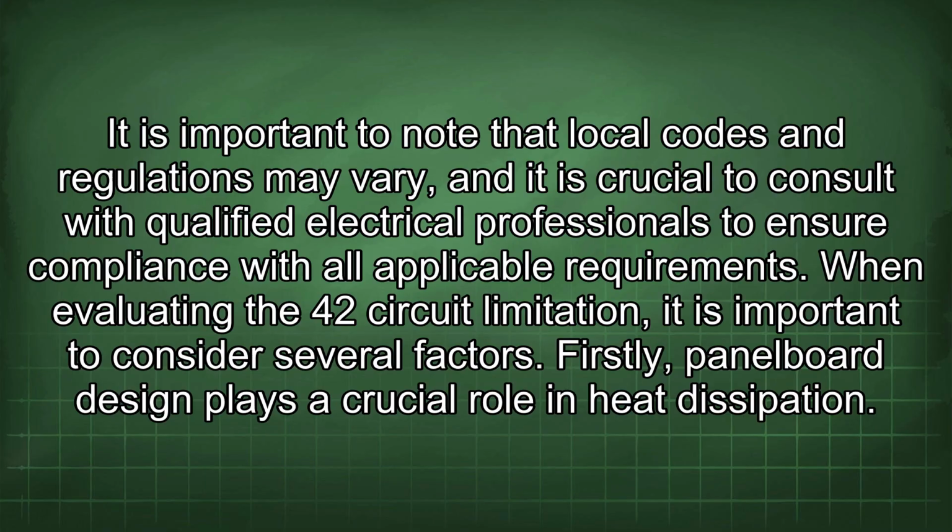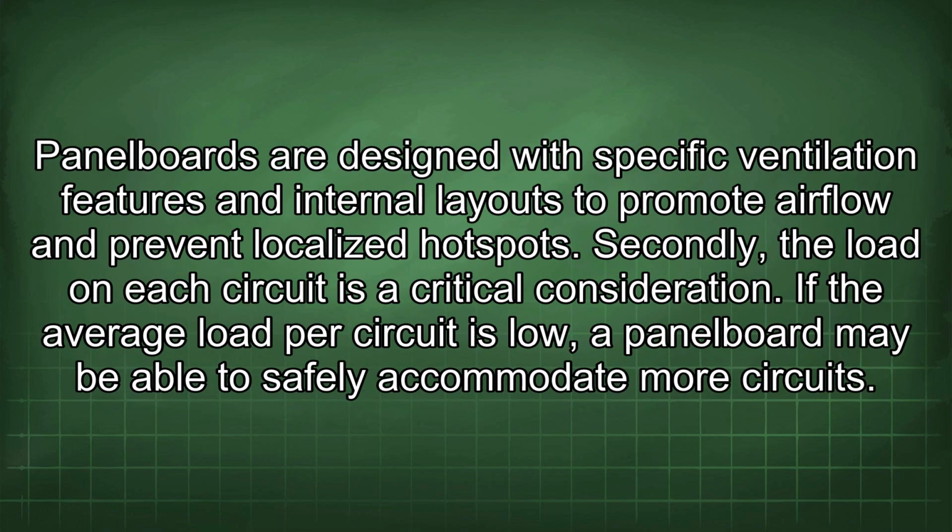When evaluating the 42 circuit limitation, it is important to consider several factors. Firstly, panel board design plays a crucial role in heat dissipation. Panel boards are designed with specific ventilation features and internal layouts to promote airflow and prevent localized hotspots. Secondly, the load on each circuit is a critical consideration. If the average load per circuit is low, a panel board may be able to safely accommodate more circuits.